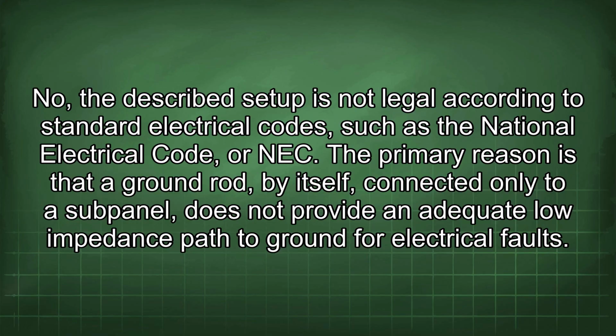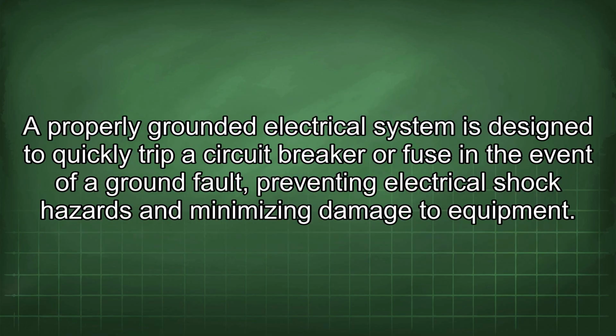The primary reason is that a ground rod, by itself, connected only to a subpanel, does not provide an adequate low impedance path to ground for electrical faults. A properly grounded electrical system is designed to quickly trip a circuit breaker or fuse in the event of a ground fault, preventing electrical shock hazards and minimizing damage to equipment.